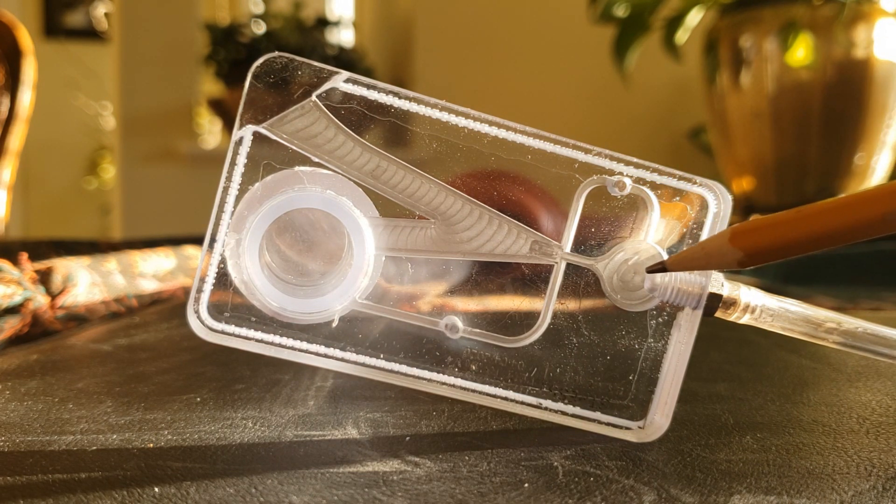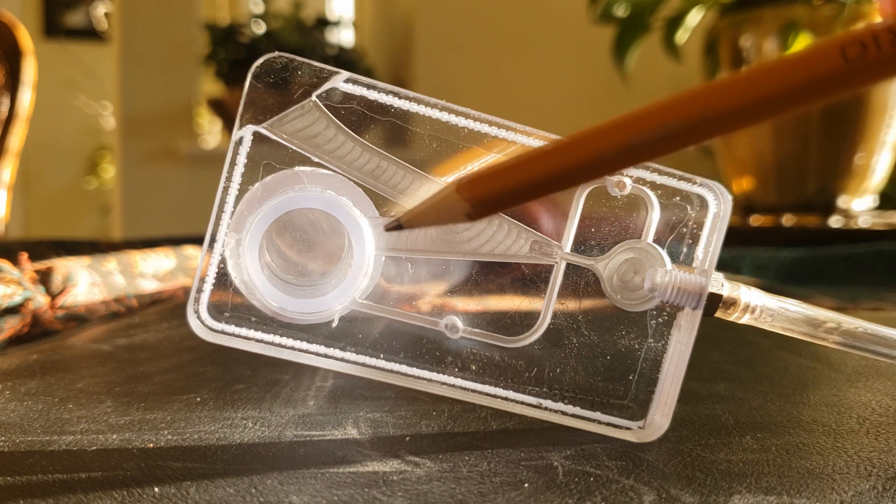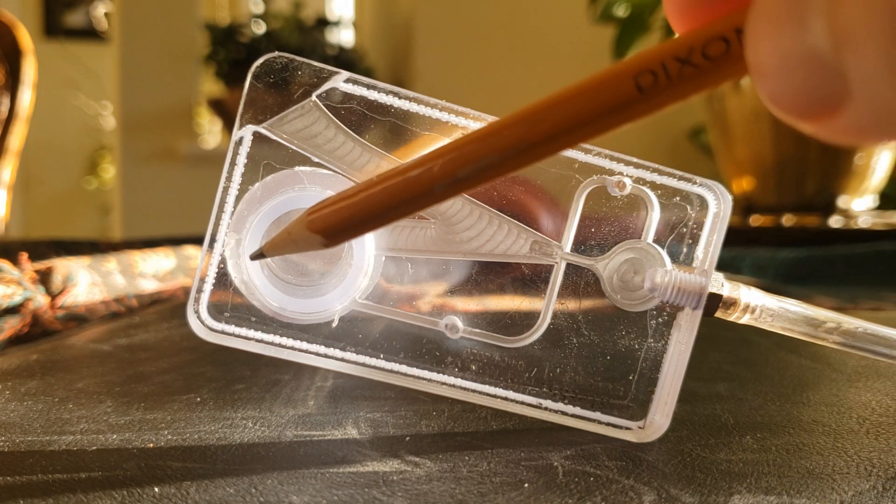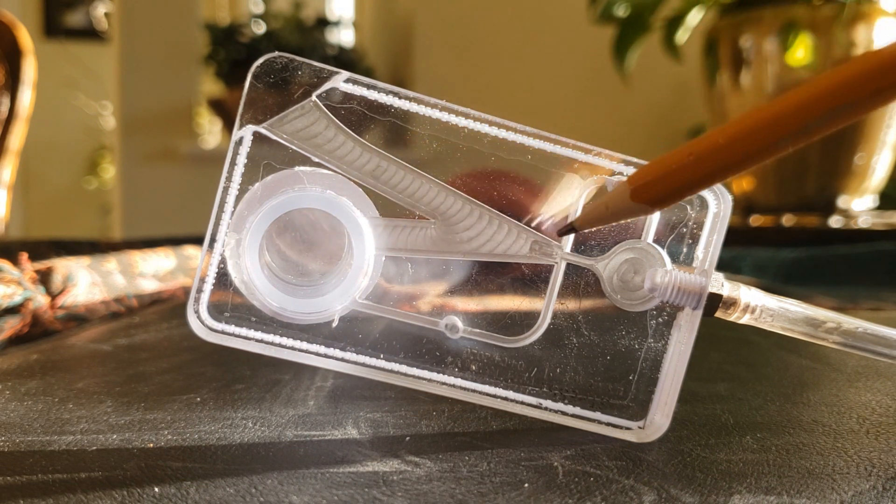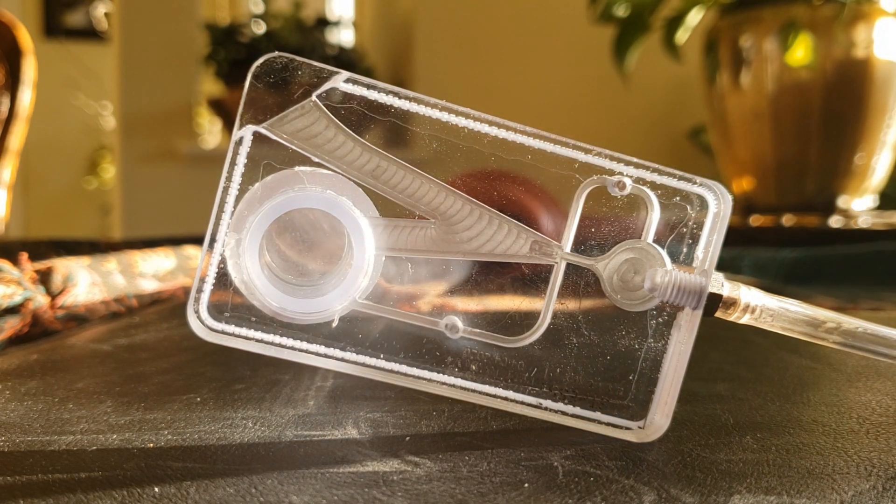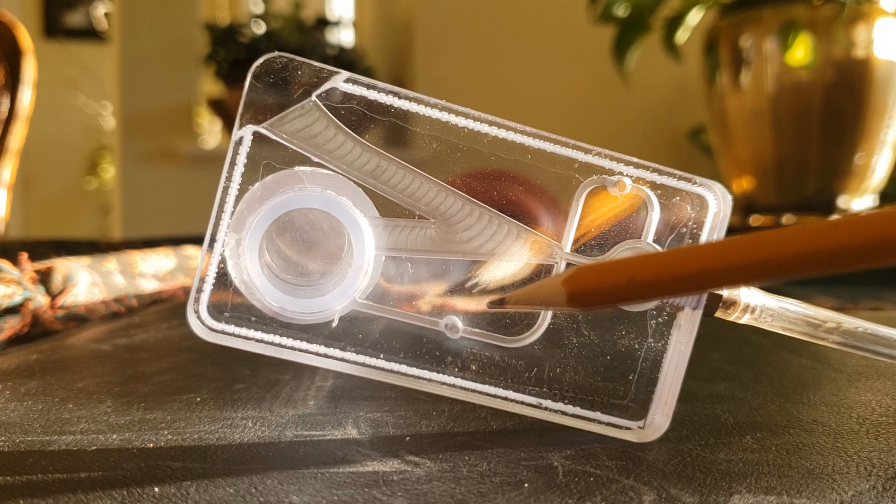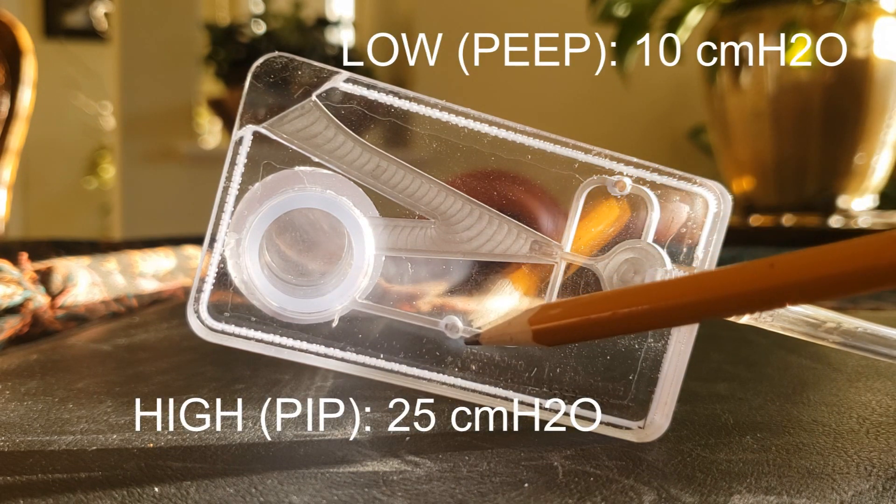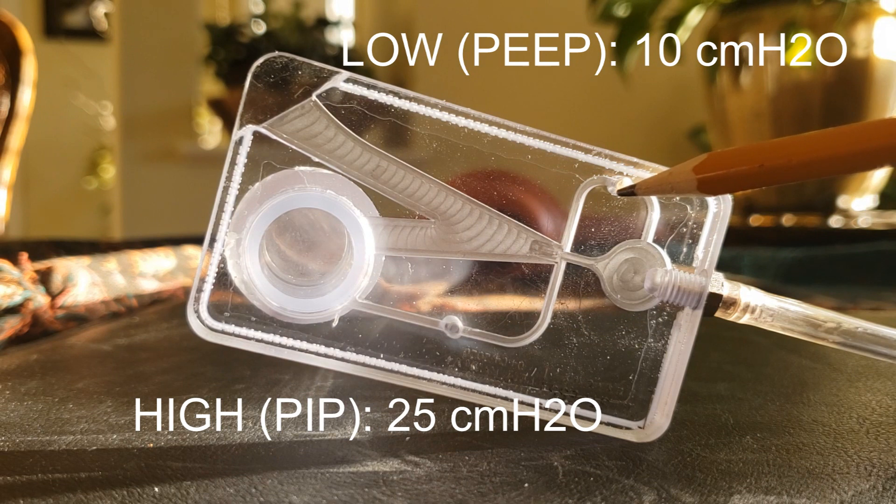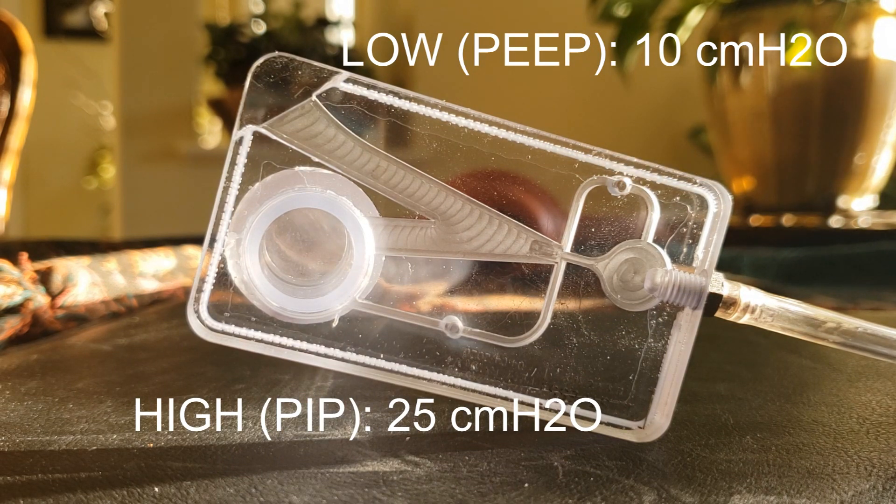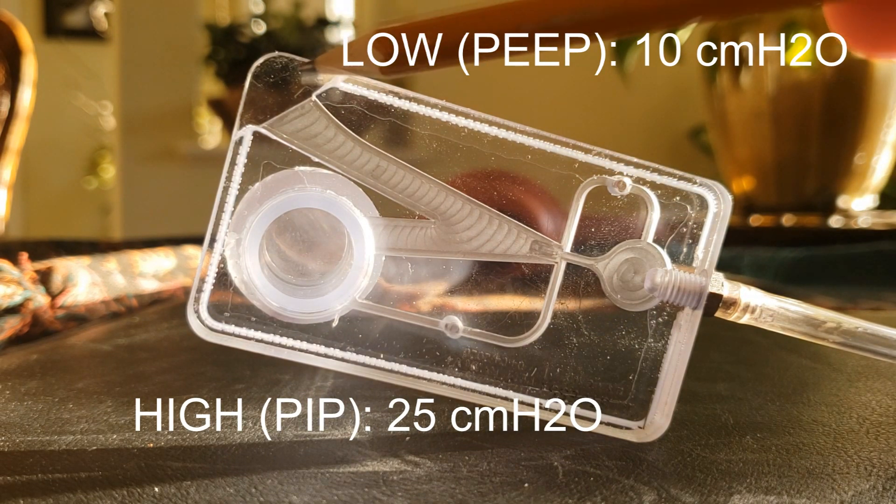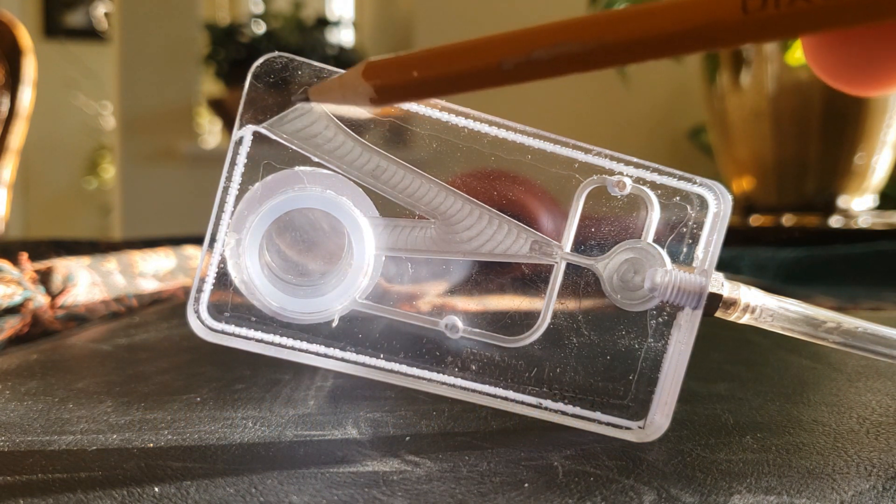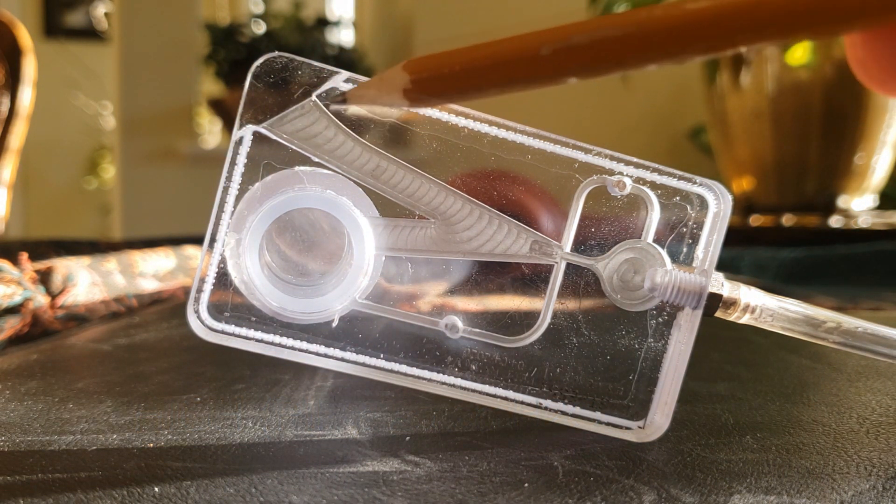This device does one thing and does one thing only. It takes a high pressure stream of air and switches it from one side to another. It does this at pressures that are determined by these set screws for high and low pressure control. And then we can also partially close the exhale port to set a particular timing for this.